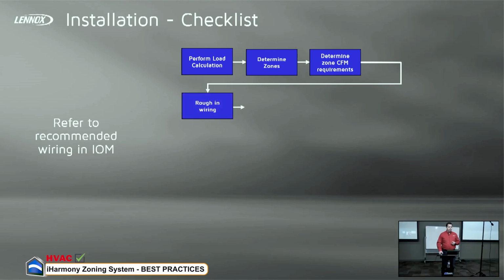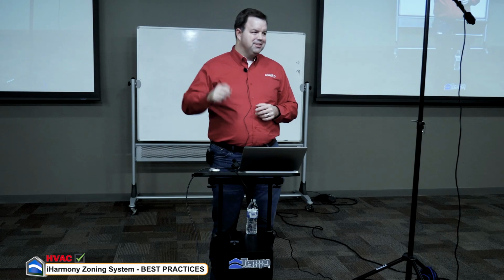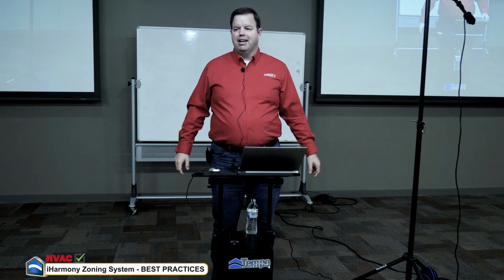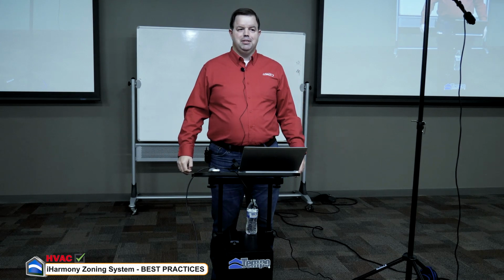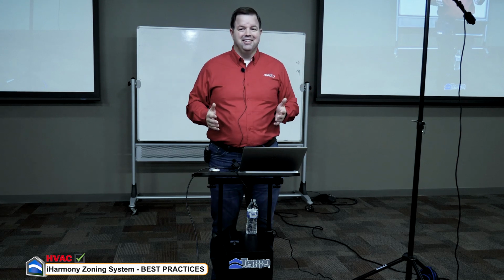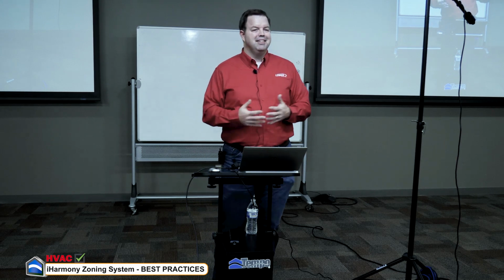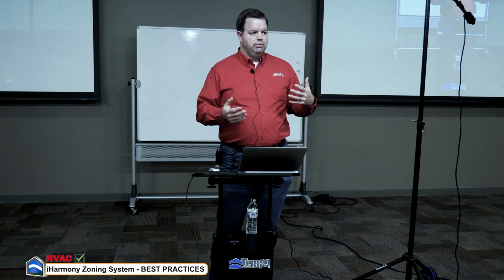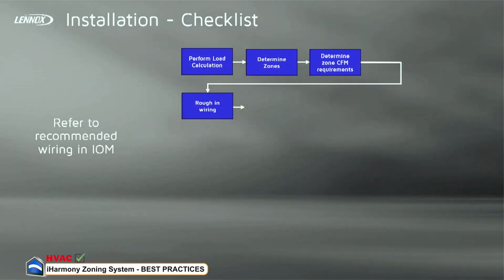And, you know, I always tell guys, I remember when I was in tech support, I got that call a lot from new dealers, guys who are just getting into zoning, and they're like, hey, what do I set this zone CFM to? I don't know, man. I'm 1,000 miles away in a cubicle. That's something that's supposed to be done through the load calc. So that's something we want to have nailed down before you get there: how to split up these zones and make sure everything's going to function properly.